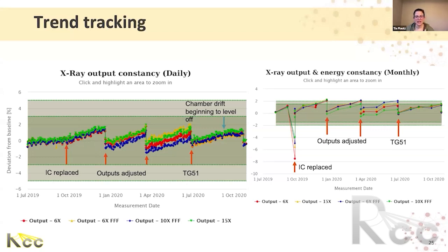Instead of making a bunch of redundant measurements with different tools, it will require a very careful evaluation of the history of your tests and a very careful evaluation of how you want to set your tolerance levels in order to ensure that anytime anything deviates from normal, you're looking into that.